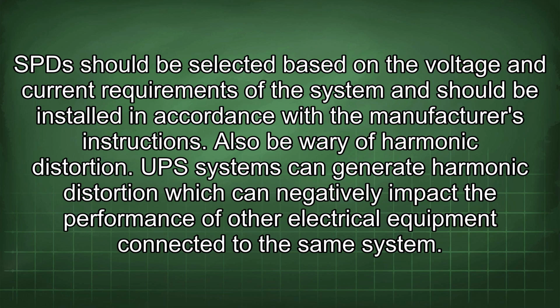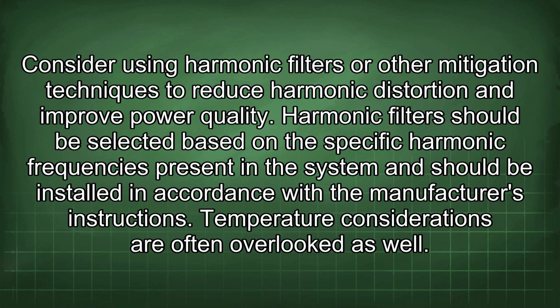UPS systems can generate harmonic distortion, which can negatively impact the performance of other electrical equipment connected to the same system. Consider using harmonic filters or other mitigation techniques to reduce harmonic distortion and improve power quality. Harmonic filters should be selected based on the specific harmonic frequencies present in the system and should be installed in accordance with the manufacturer's instructions.